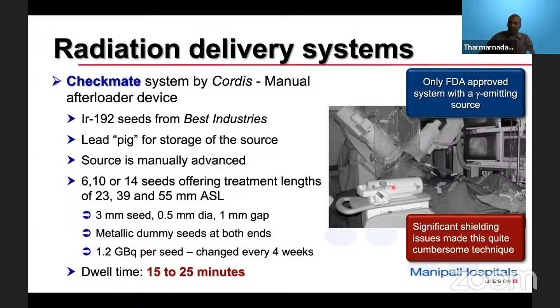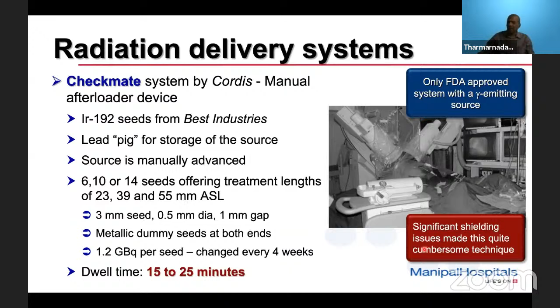It is the only FDA approved system with a gamma emitting source, and significant shielding issues made this quite a cumbersome technique. It has to be retracted and then pushed from this lead pig. I remember at All India Institute we had to keep several mobile lead shields all around the patient in order to reduce the dose to personnel standing in the console room of the cath equipment. Without that, the radiation exposure rate at the control console will be quite high. So we had to move heavy lead shieldings, fabricate them and keep them inside the cath lab. Always with iridium 192, that is the problem.